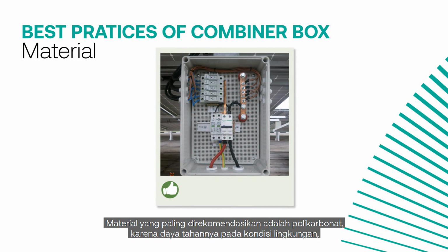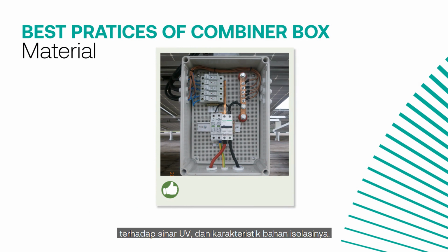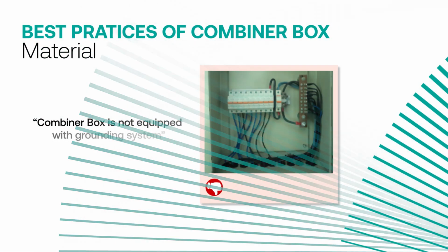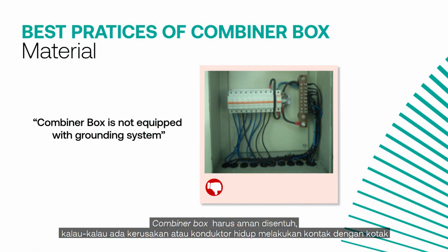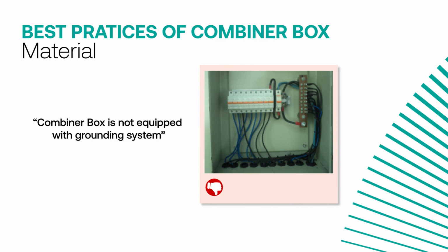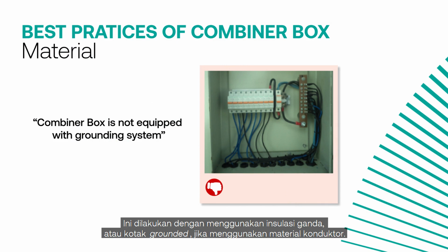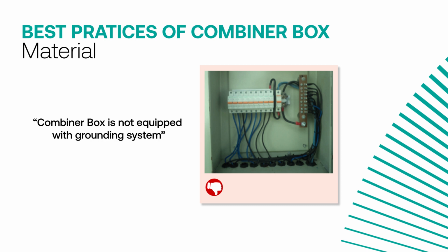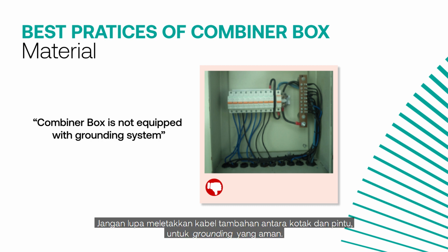There are two types of material that make a good enclosure: polycarbonate and metal. The most recommended material is polycarbonate due to its durability in a wide range of environments, resistance against UV, and characteristic as an insulating material. The combiner box must be safe to touch in case of a fault or if a live conductor makes contact with the box. This could be achieved by having double insulation or a grounded box if conductive material is used. Do not forget to put an additional wire between the box and door to obtain safe grounding.